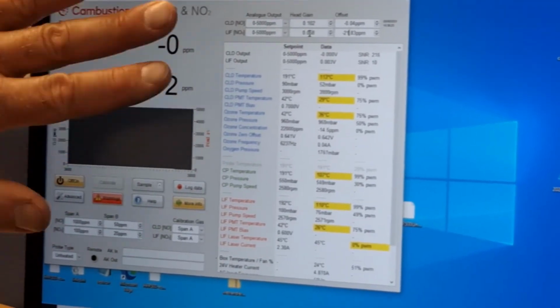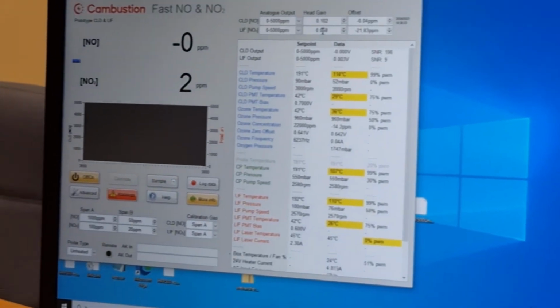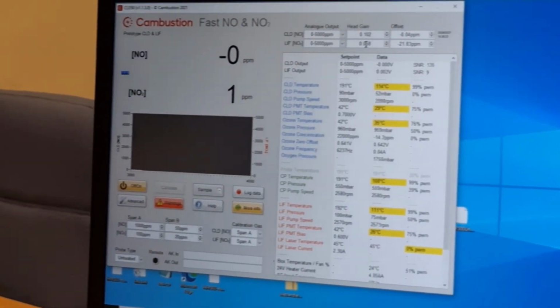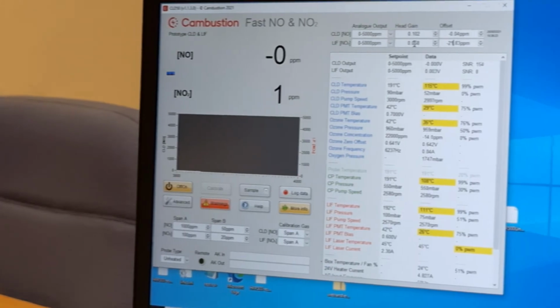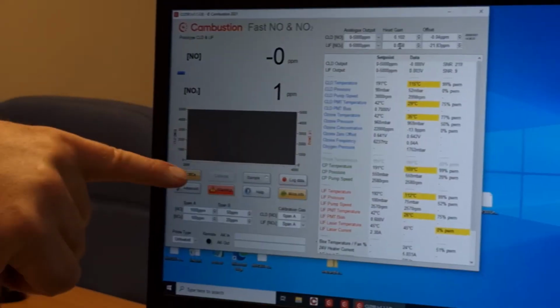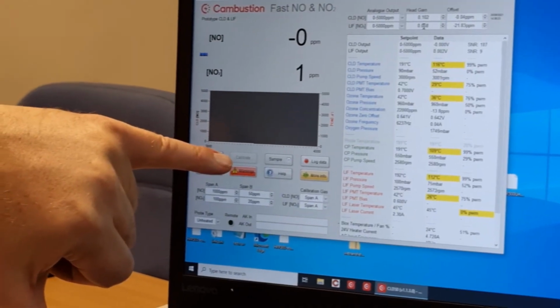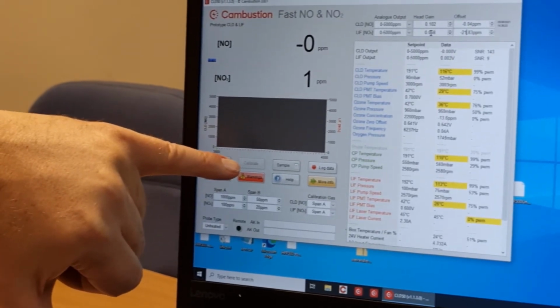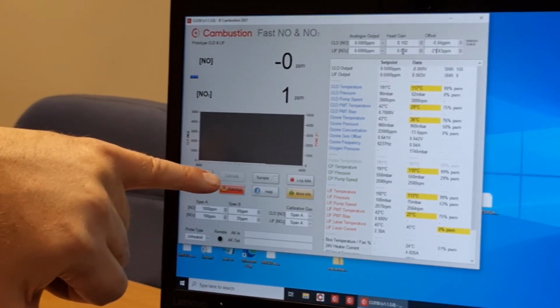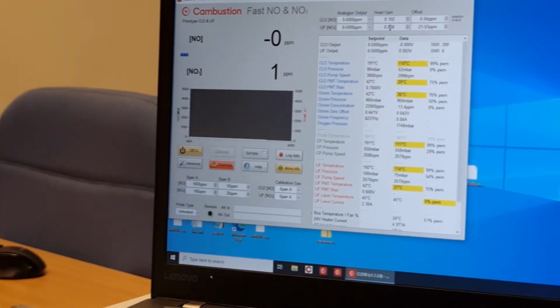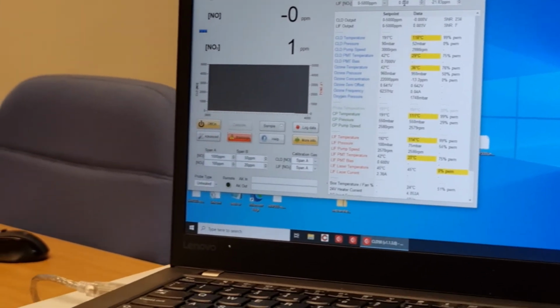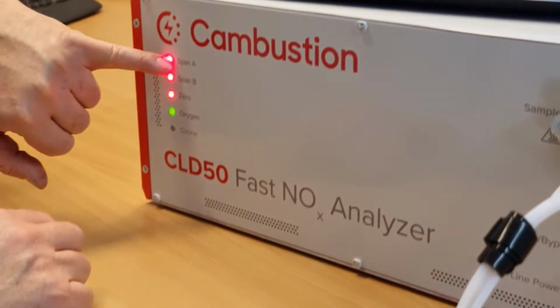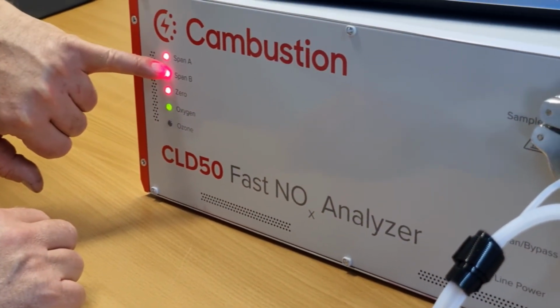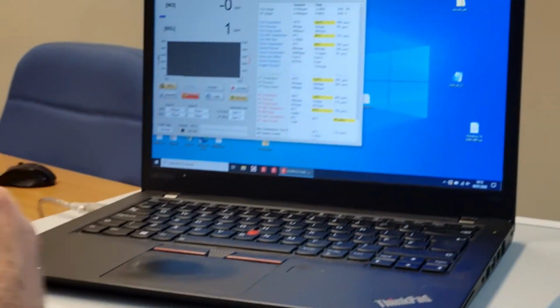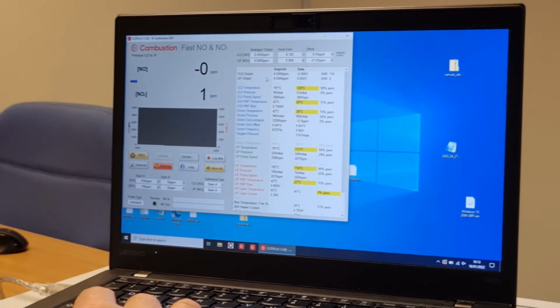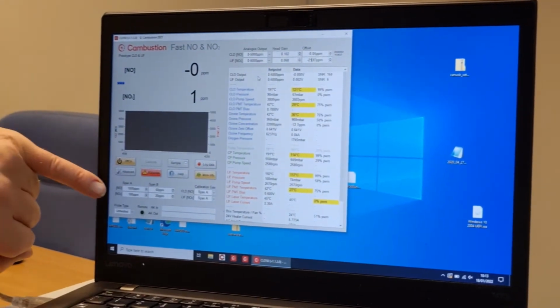These things are moving around at the moment because things are still warming up. When the equipment is stable and all of these parameters are in control, this calibrate button becomes available. If you want to use the auto calibrate one button function, this requires the cal gases to be connected to the rear panel, and our LEDs here would indicate which gases have been switched on and pressurized. Then you would have to enter the calibration gas values into the software, and these are shown down here.